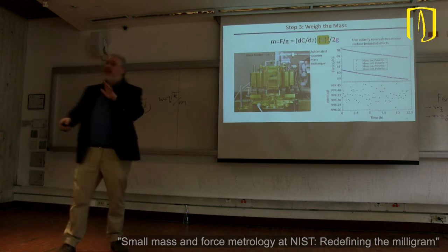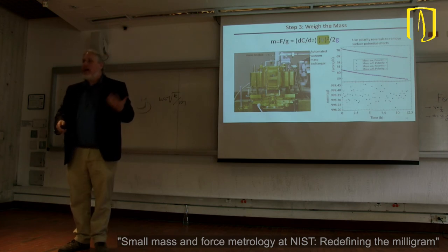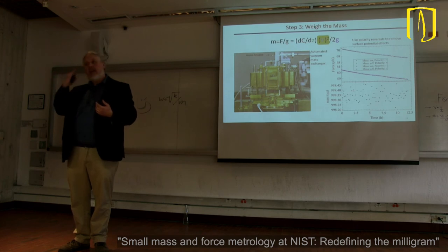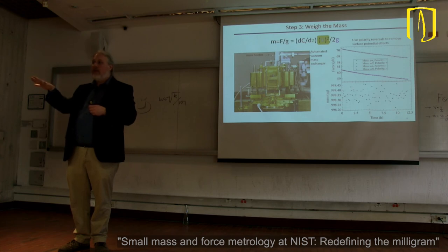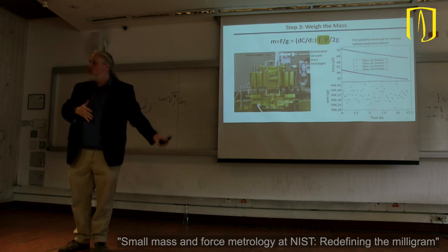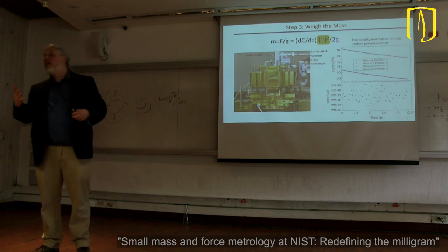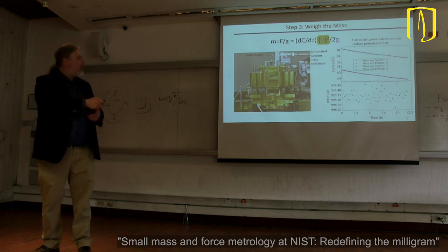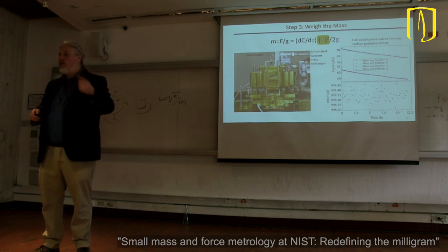And so the other things are a little bit more subtle, perhaps. So the alignments, we just think about, okay, if we want our force to be parallel to gravity, we have to align it, and we measure how closely it's aligned to gravity. So we can measure those things and take them into account. We measure temperature of the balance, right? So when I say our limiting factor in our measurement is the temperature dependence of our capacitor here, it's because we're measuring the temperature while we're doing the measurements.